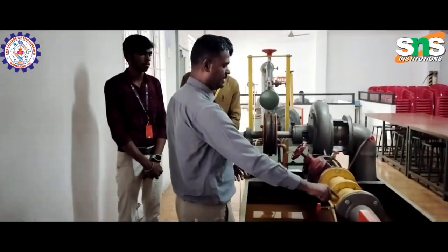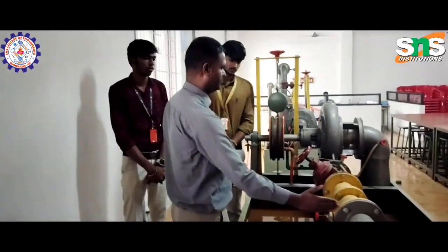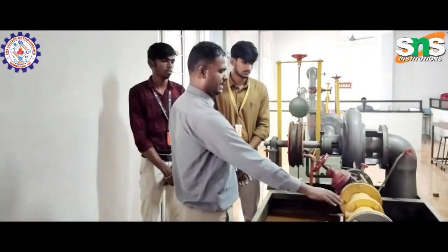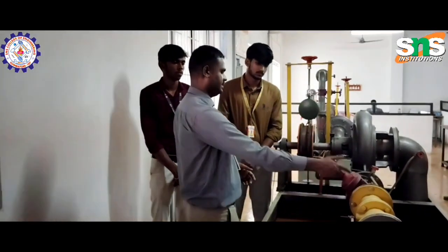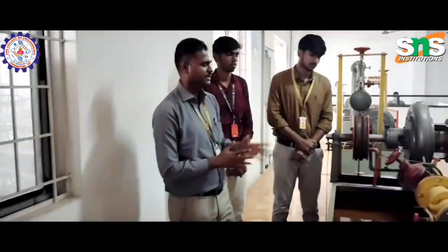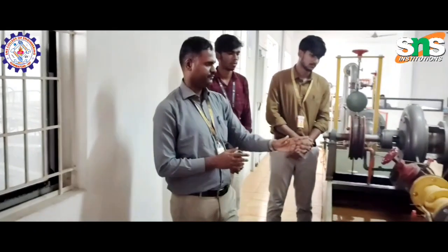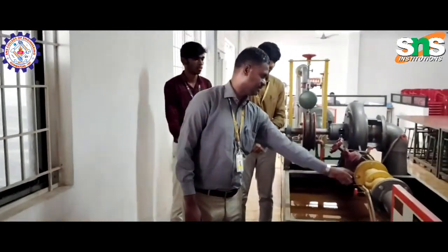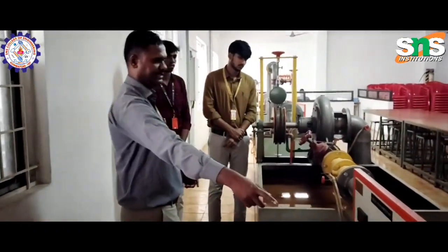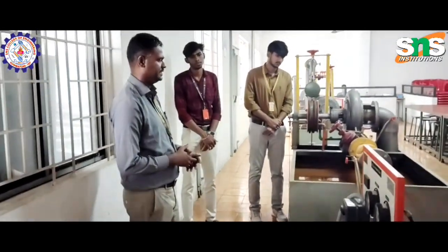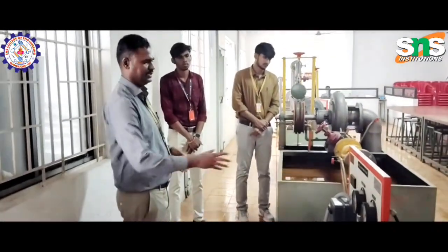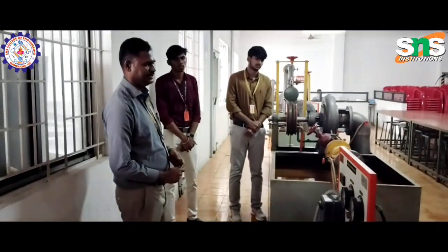One is the inlet of the venturimeter, where we have to calculate the inlet area, and this is called the throat. We have to measure the throat diameter and calculate the throat area, and we have to measure the inlet pressure and throat pressure. It is directly connected with the pressure gauge, so there is no need to use manometers or differential manometers. It is directly displayed in the reading.